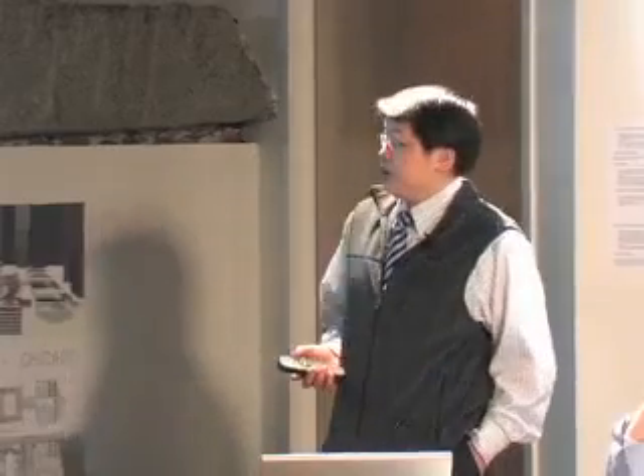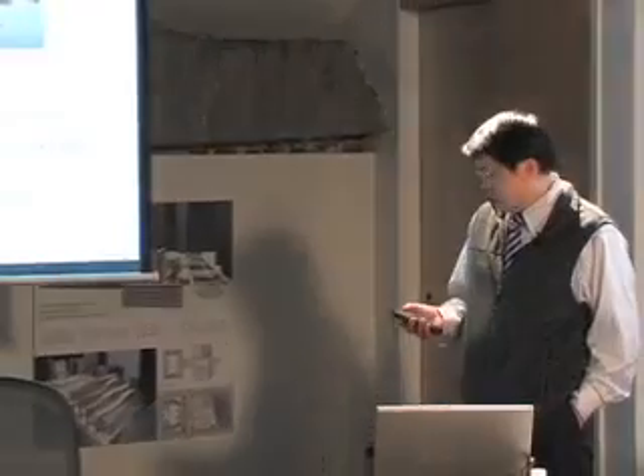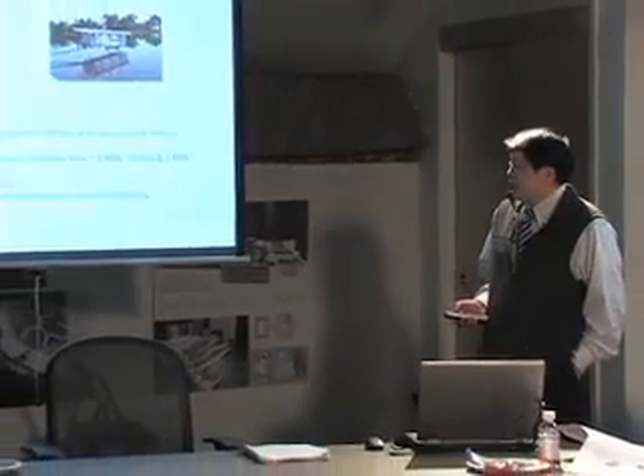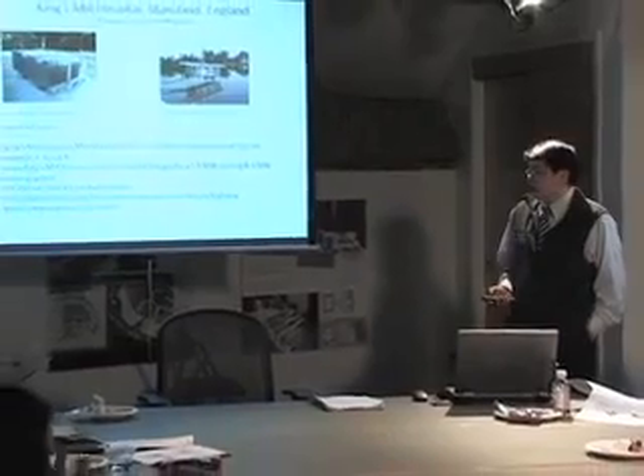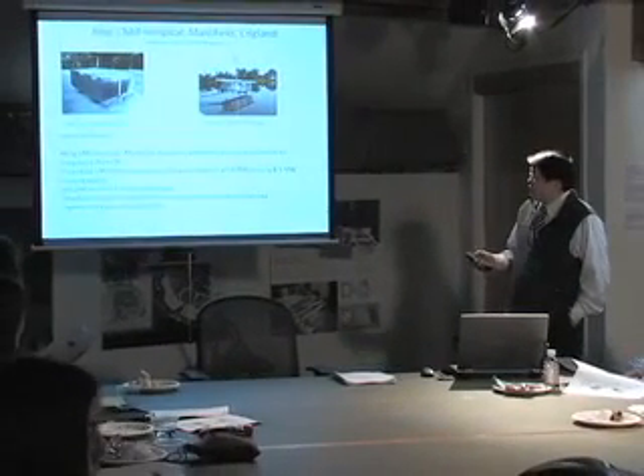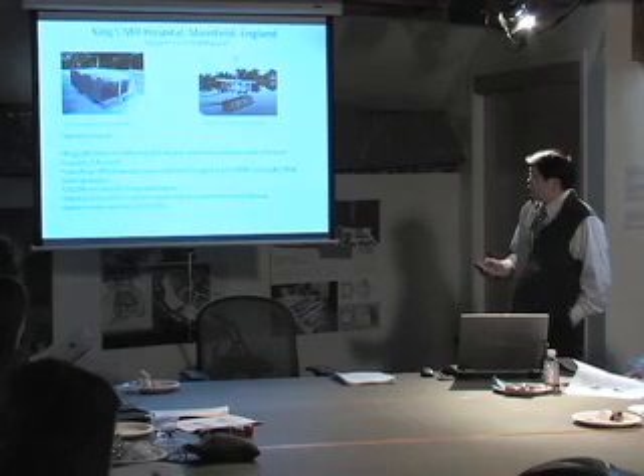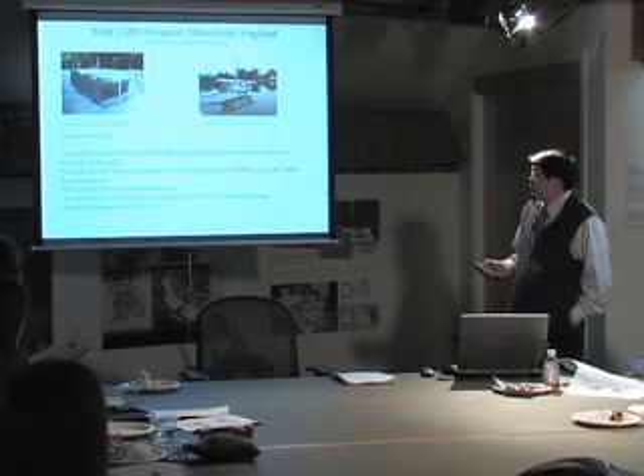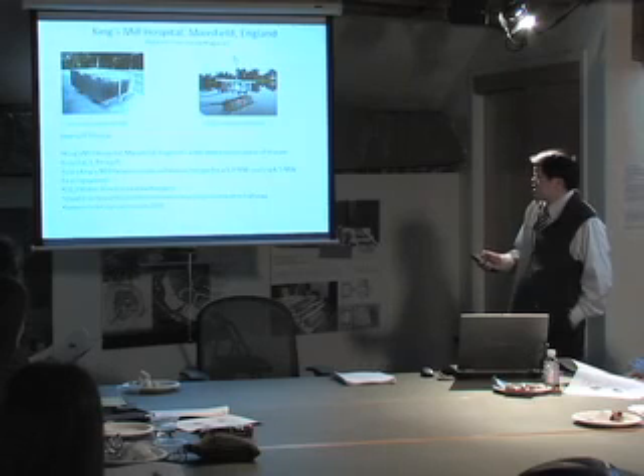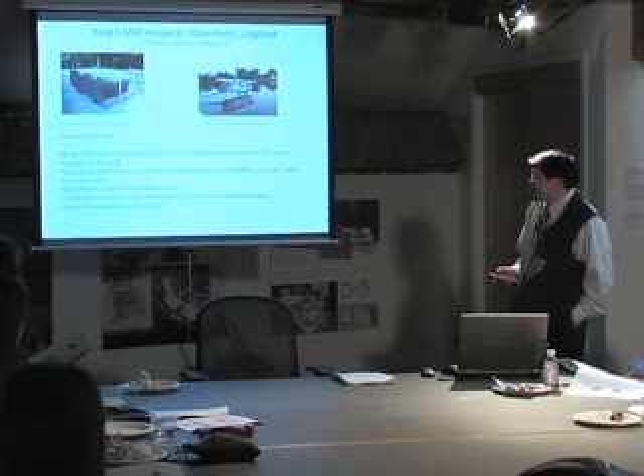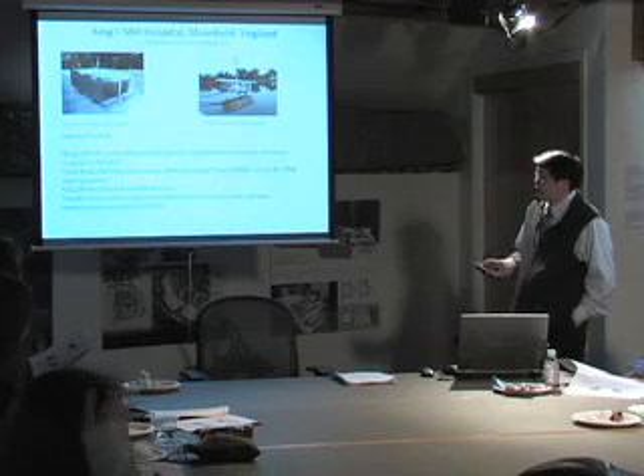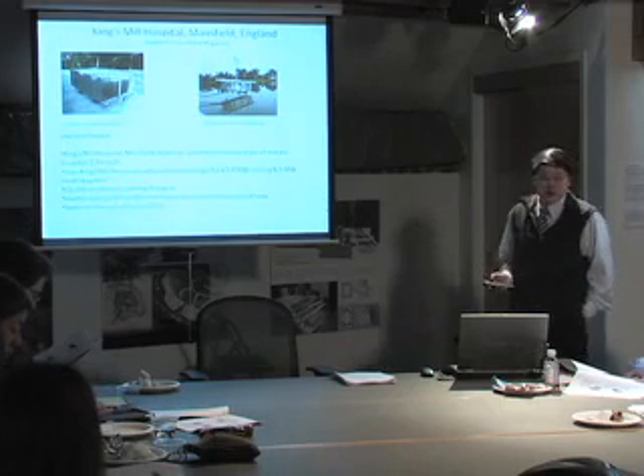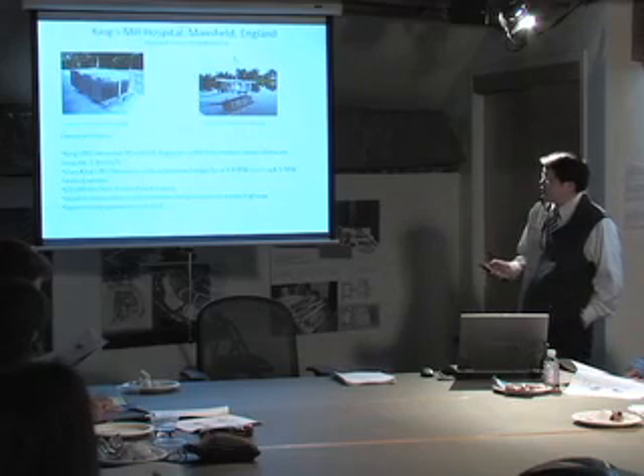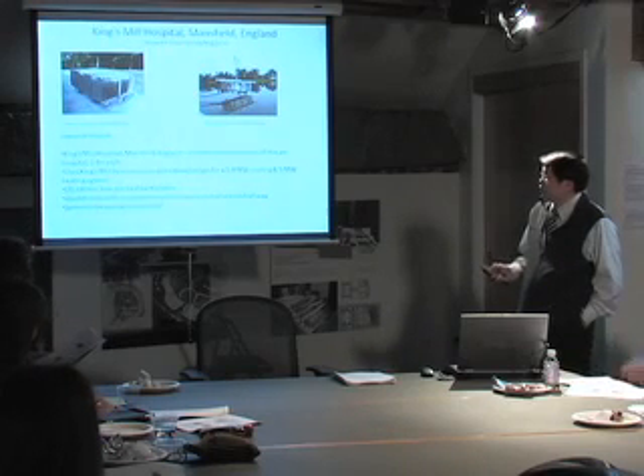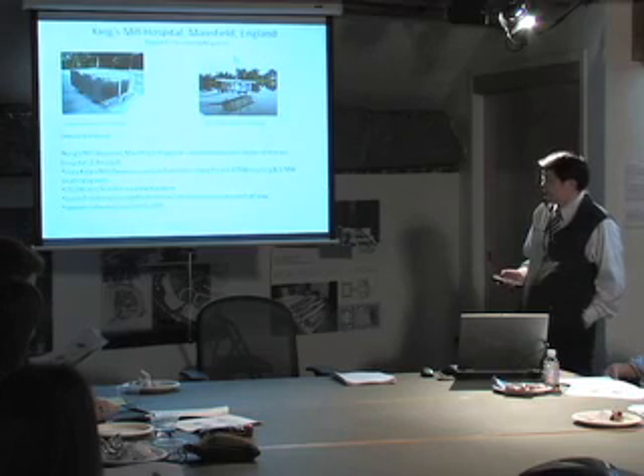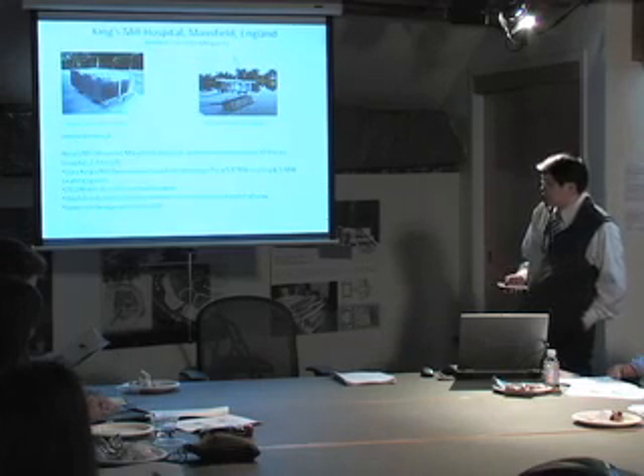This is a project in Mansfield, England. It's a hospital, a 920-bed modern state-of-the-art hospital, 1.4 million square feet. They utilize the Kings Mill Reservoir lake, and they drop seven 200-ton Slim Jim heat exchangers in the pond. The lake is across the highway from the hospital, so they utilize directional boring to run the pipes to pump the ground loop water to the heat pumps in the building. It's supposed to be running this year.